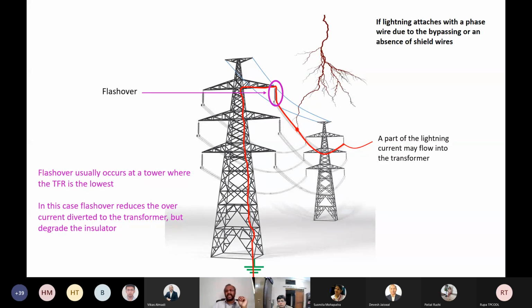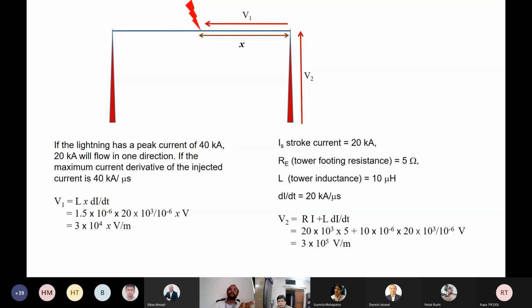Okay, now let's do a very simple calculation. If lightning strikes a power line, say a medium voltage line, a distance x away from a tower, and if the lightning has a peak current of 40 kiloamperes, 20 kiloamperes will flow in one direction. This is a very crude approximation. Let's assume that in both towers the tower footing resistance is nearly equal, so that the current will be distributed among the two towers. Now assume that this is a very hypothetical case where there are only two towers.